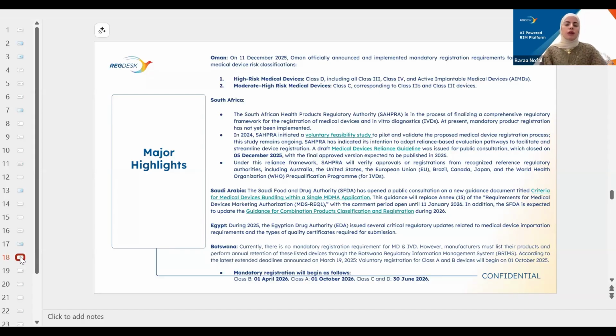classification. So by the end of that year, Oman officially announced that. So all the manufacturers, or foreign manufacturers, who are interested to register in Oman can now refer to see all the required documentation. These two guidelines were in a draft version in the middle of 2025, and recently, on 11 December 2025, they came into effect. In addition to these two laws, Oman also published a manufacturer registration guideline.